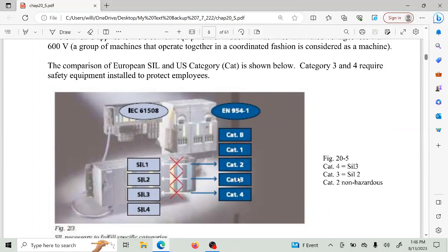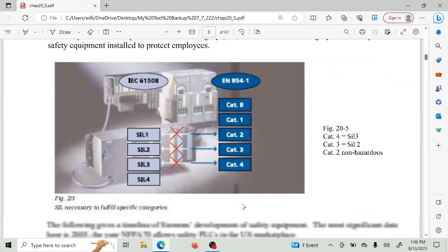Here is a listing of the various categories. In Europe they talk about SIL levels, and in the United States they talk about categories. Category three and four require safety equipment; categories two, one, and B do not. The equivalent of category three is SIL 2, and category four is SIL 3. There's also a SIL 4 in Europe. Below that line — SIL 2 or category three — you must use safety equipment.